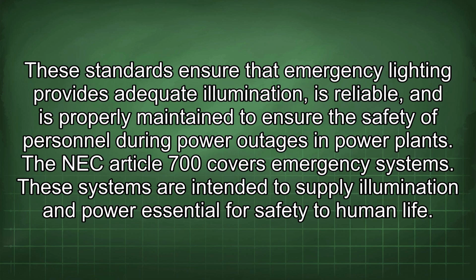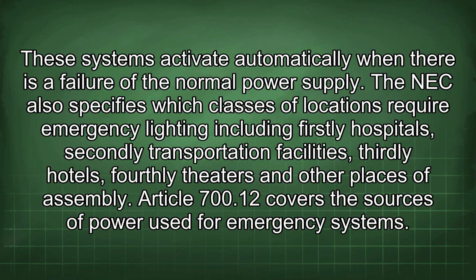The NEC Article 700 covers emergency systems. These systems are intended to supply illumination and power essential for safety to human life. These systems activate automatically when there is a failure of the normal power supply. The NEC also specifies which classes of locations require emergency lighting, including firstly hospitals, secondly transportation facilities, thirdly hotels, fourthly theatres and other places of assembly.